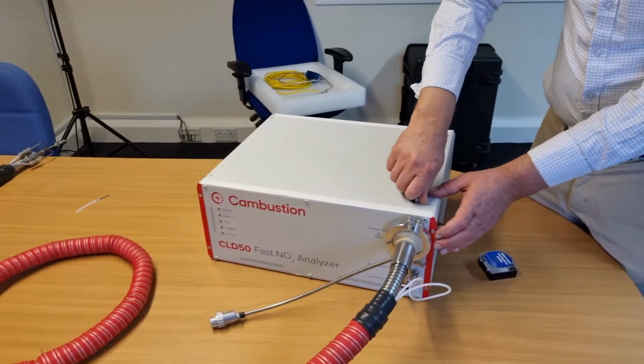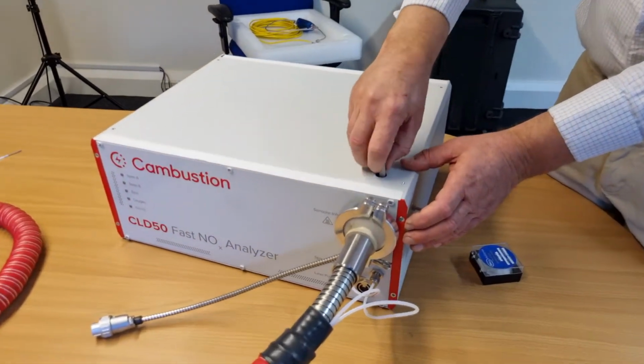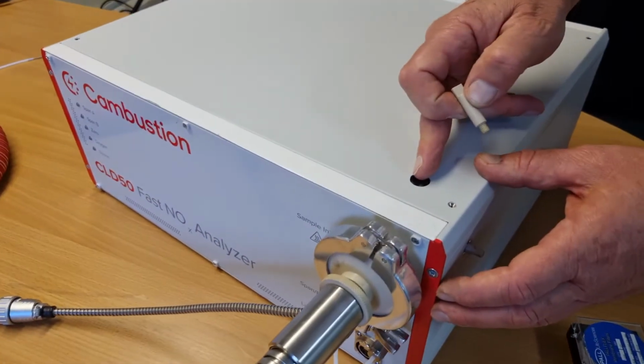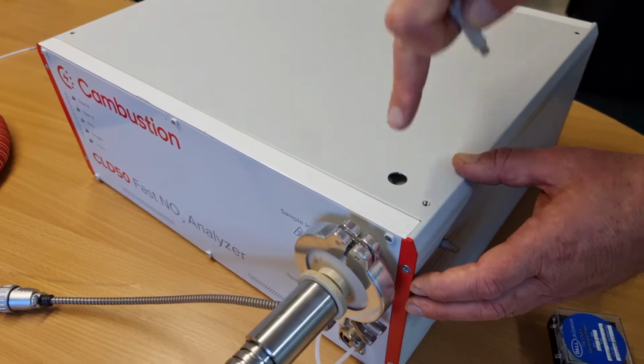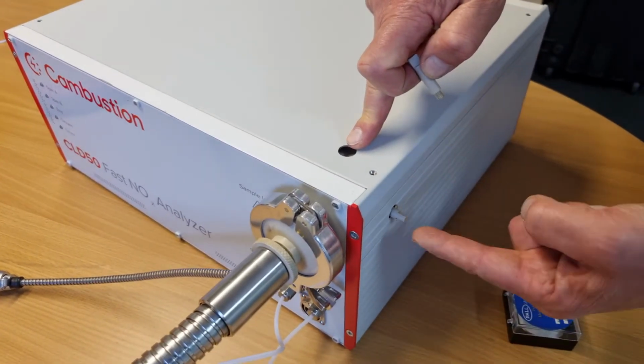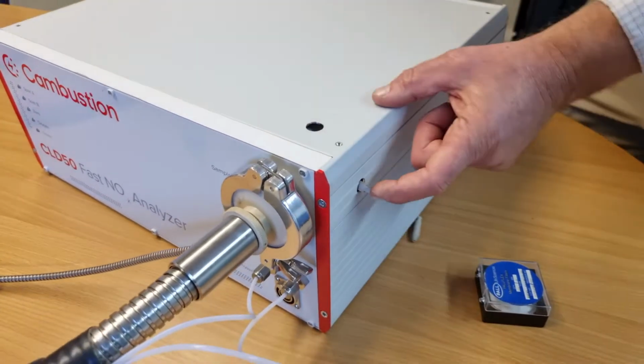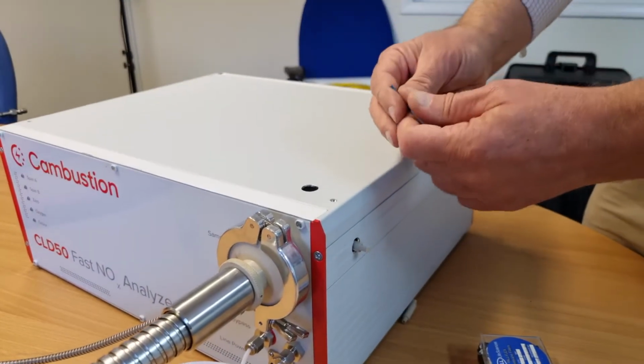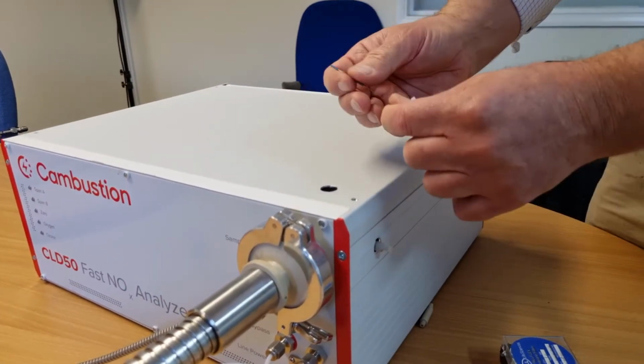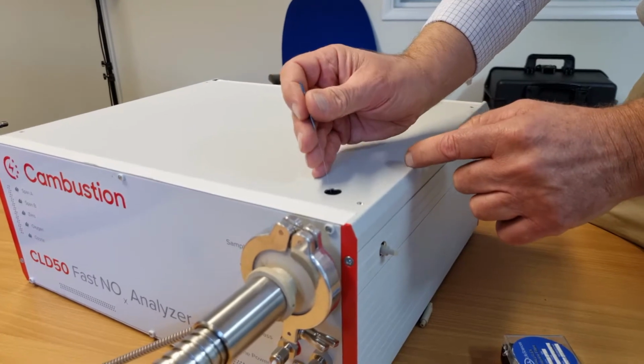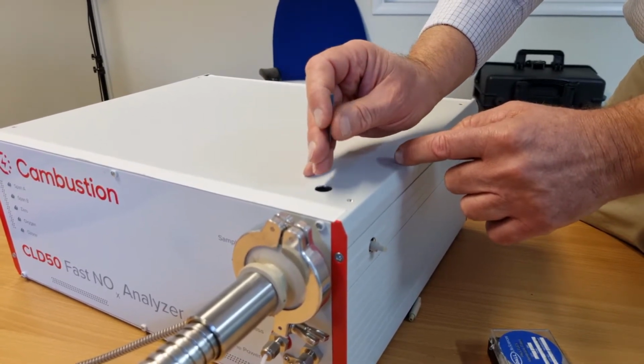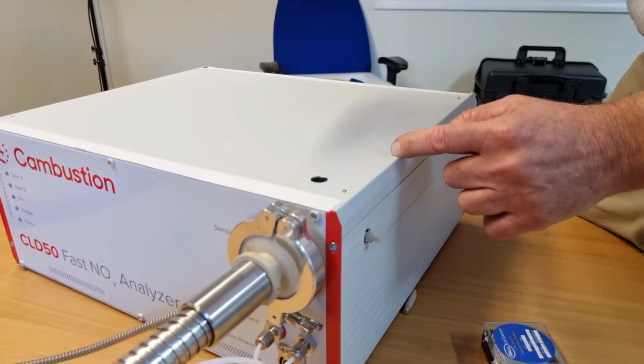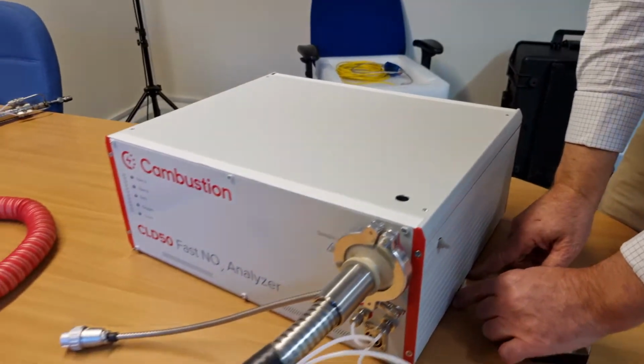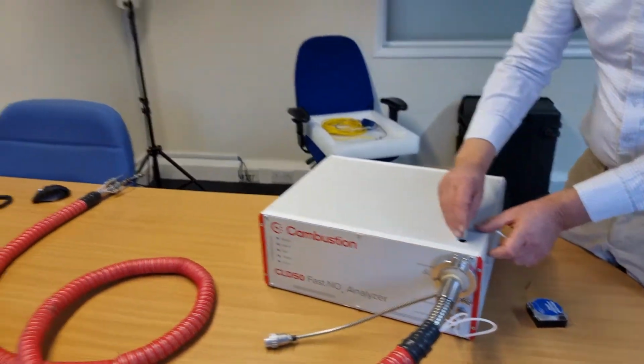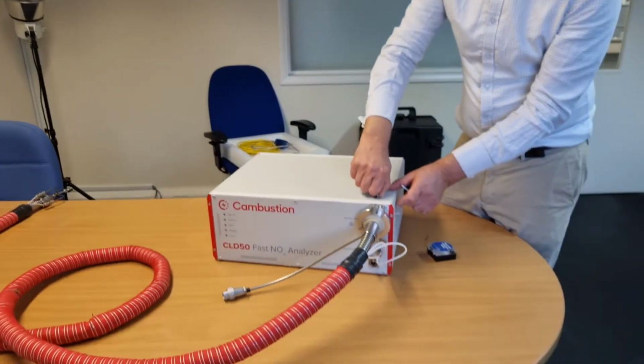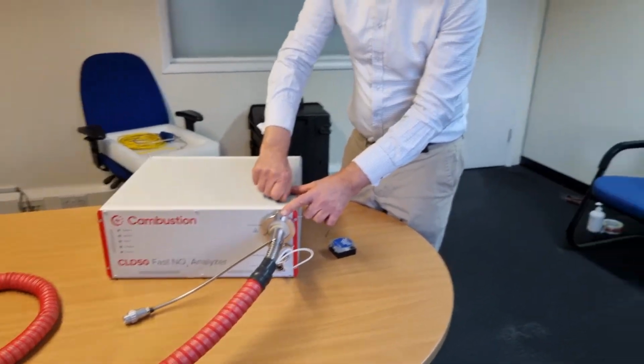If you decide to run without a filter, and if you get some contamination in the analyzer, the capillary is accessible through the cleaning ports. There's one vertically for the LIF, and there's one horizontally in the side of the analyzer for the CLD. You can clean through those capillaries using a cleaning wire that's provided in the toolkit, and you push that down through the capillary and clean it out like that. But if you're subject to that level of contamination, it's better just to run with the filter in situ anyway.